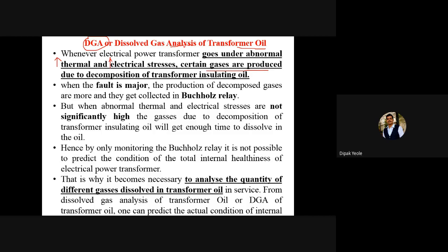If the transformer oil gets decomposition because of these stresses, there is a possibility of certain gases being produced. If the fault is major — meaning because of uncontrolled increase in temperature or uncontrolled increase in current, which is nothing but a fault — then the production of decomposed gases is more. These gases get collected in the Buchholz relay. What is the Buchholz relay? Let me share my screen and explain, because if you don't understand what the Buchholz relay is, there is no point studying dissolved gas analysis.